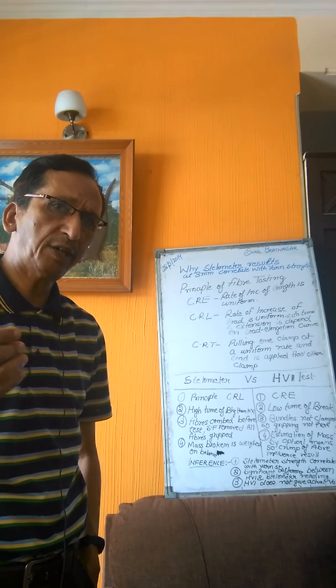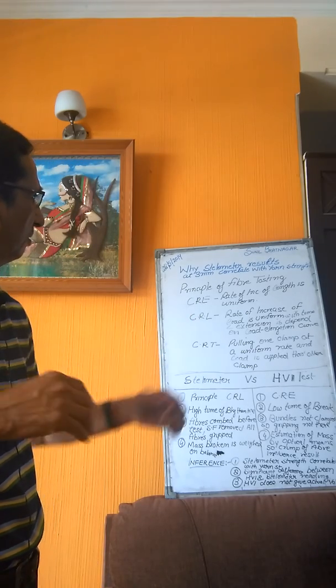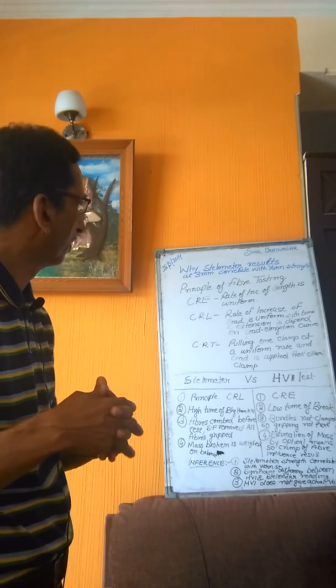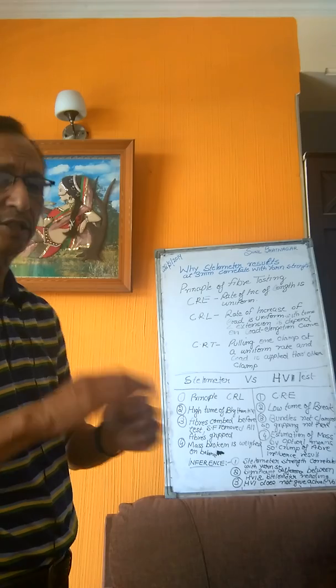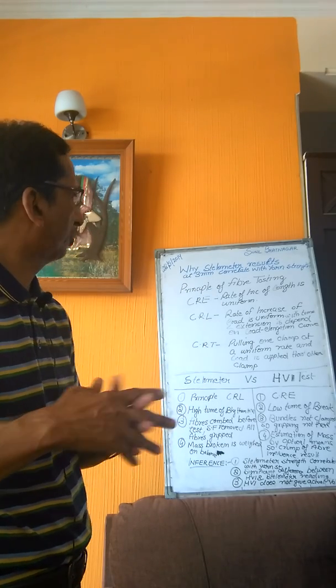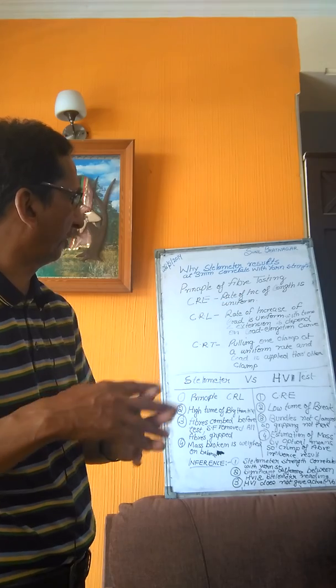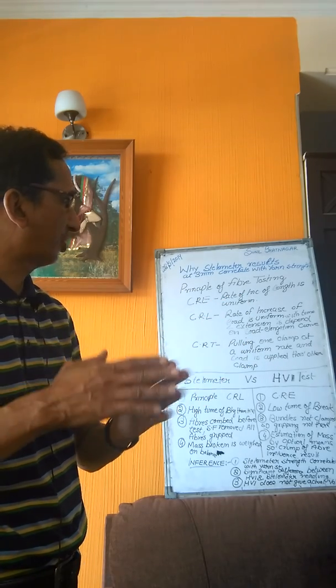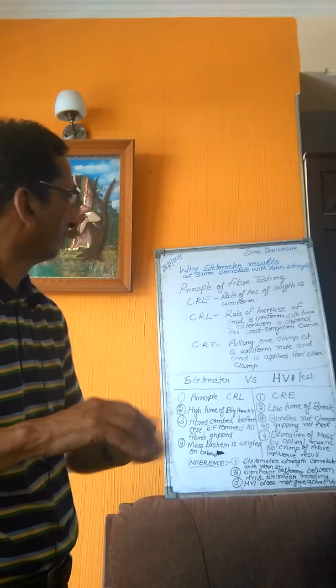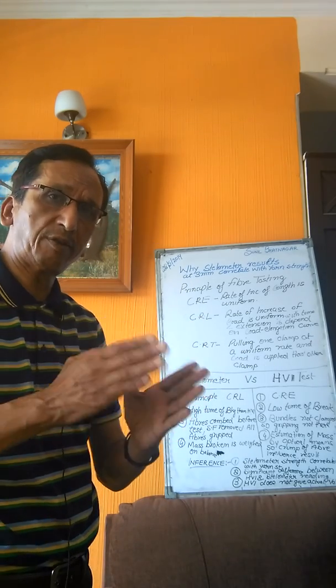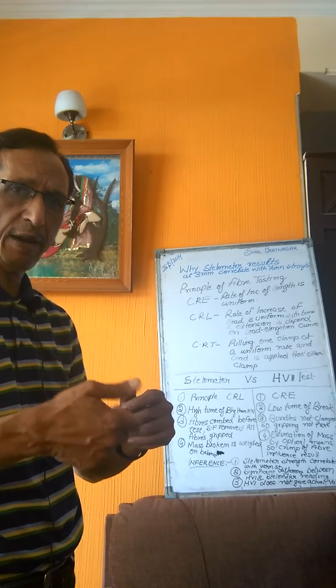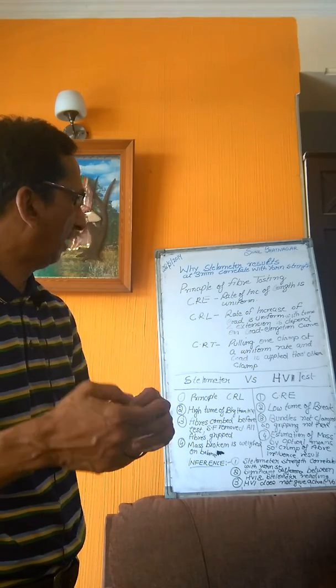Testing equipment like Pressley, Stelometer, and HVI are based on certain principles. The first is Constant Rate of Extension (CRE), where the rate of increase of length is uniform with time. The second is Constant Rate of Loading (CRL), where the rate of increase of load is uniform with time and extension depends on the load-elongation curve. The third is Constant Rate of Traverse (CRT), where load is applied through one clamp pulling at a uniform rate.